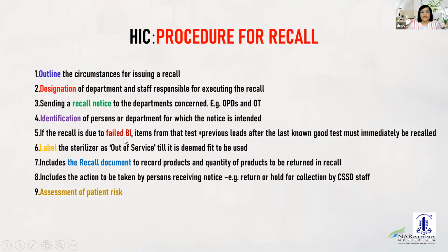If there is a failed BI, items from that test plus previous loads after the last known good test must be immediately recalled. Label the sterilizer as out of service. Include the recall document to record products and quantity of products to be returned in the recall. Include the action to be taken by persons receiving the notice, that is return or hold for collection by CSSD staff, and assessment of patient risk.